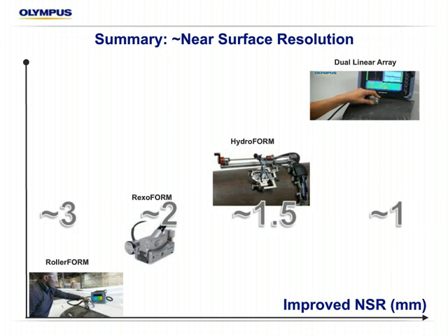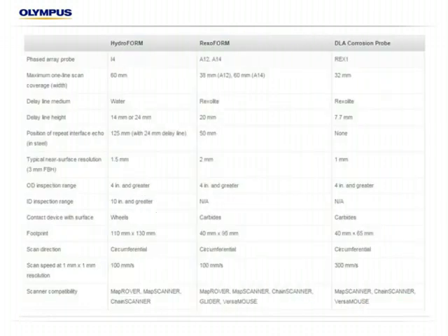So, a little bit another comparison table. I won't go through it all, just point out a few quick things. So scan speed, typically for all these, we baseline them with a resolution of 1 millimeter by 1 millimeter. So in that, we're talking about the scan axis and the index axis. So when you get the data back, you're able to look at every millimeter in both directions, and that's your resolution scale.